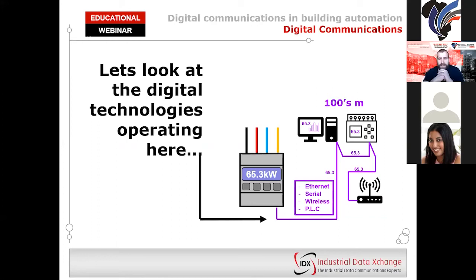There are two main categories of communication protocols operating in this LAN environment. The first is called a proprietary protocol. These are typically locked into a single manufacturer or vendor, and the standards are not published or made available to other manufacturers to implement. This is a challenge because it gives the user very little flexibility to choose the best components for the application. In other words, if you bought a device from manufacturer A, it typically wouldn't communicate with anything other than manufacturer A devices or systems. That's a problem—it gives these companies a bit of a monopoly, which hurts price, compatibility, and flexibility to optimize your application.